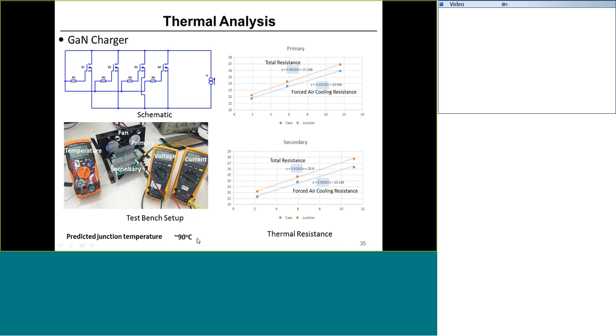Based on our test, we find the 4 switches in parallel will exhibit 0.6 degrees per watt. Given the overall loss, we might reach a projected temperature of 90 degrees C when ambient is about 70 degrees C. For the silicon carbide charger, we assign 2% efficiency loss for all the switches and 1% for the transformer.